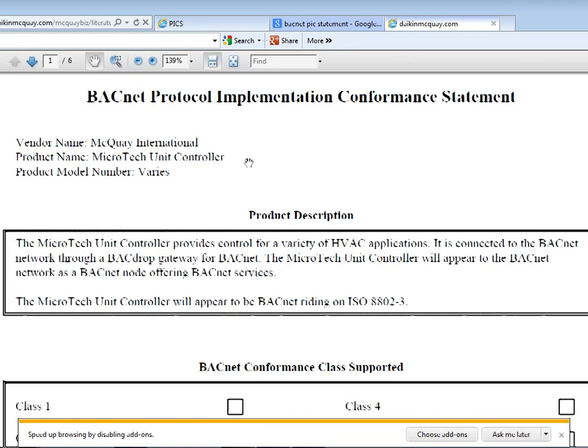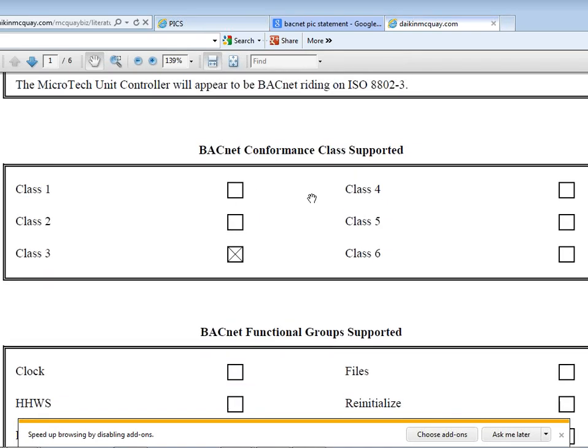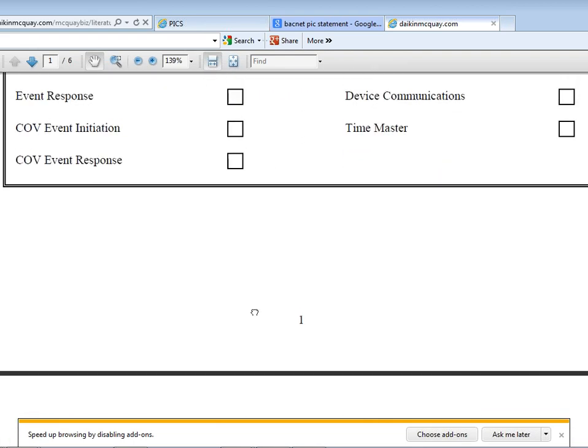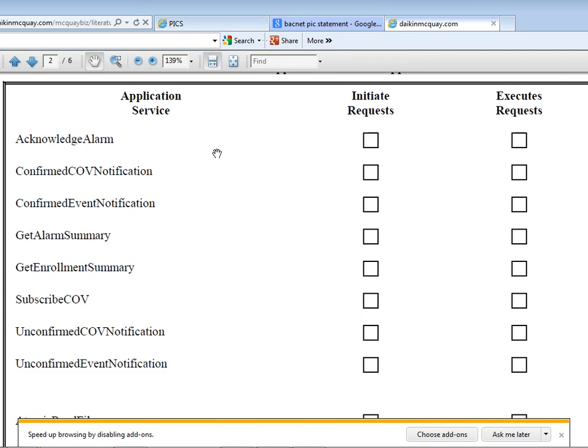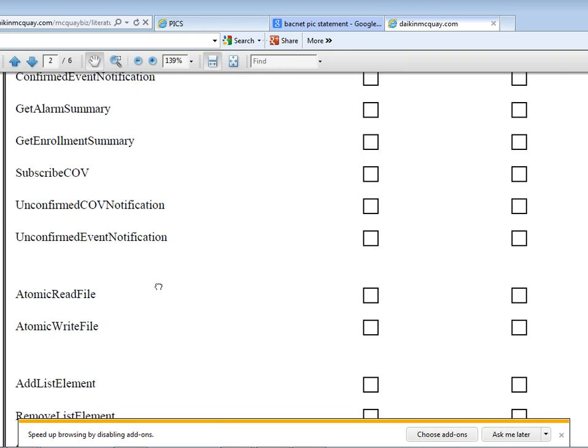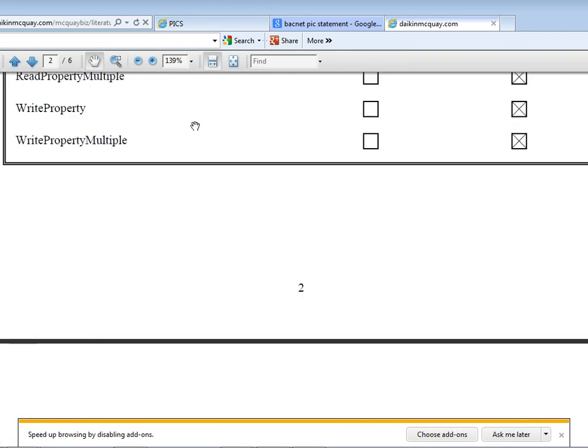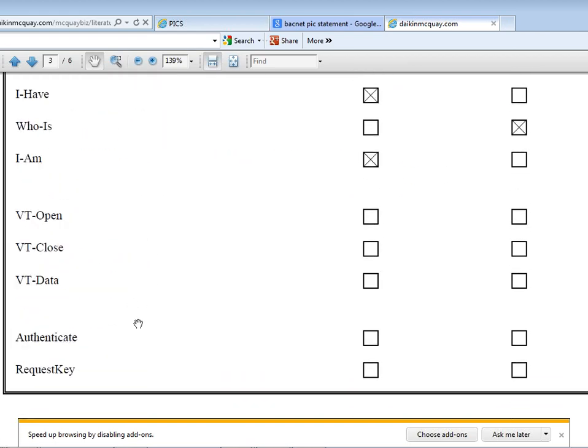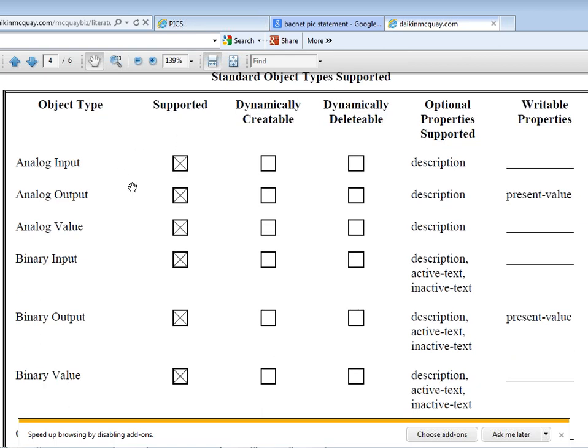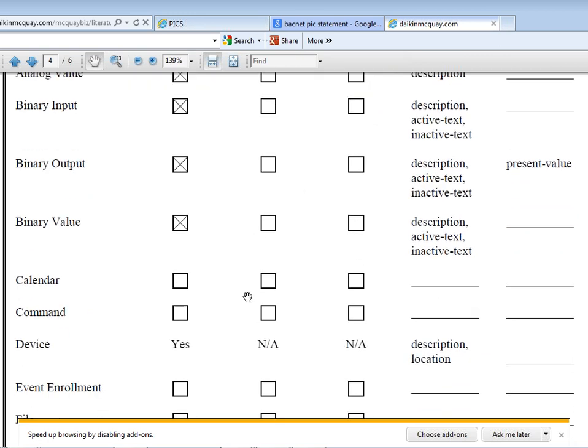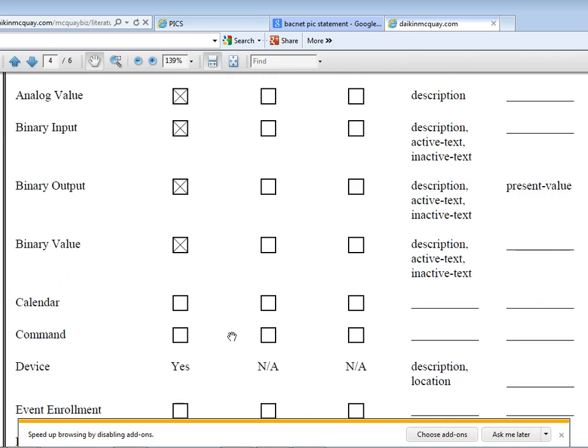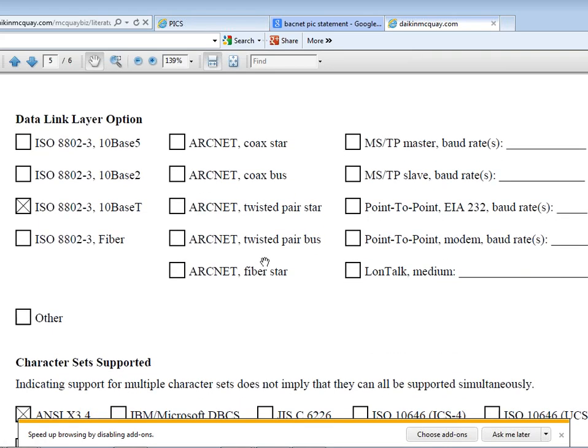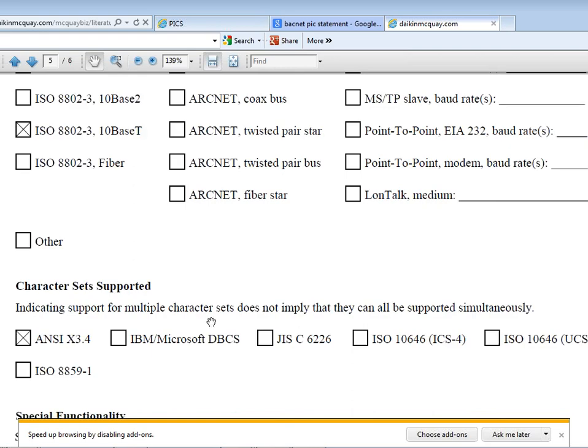This looks like a McQuay PIC statement. You've got your vendor name, product name, the class of BACnet conformance, functional group supported - these are the different types of services they can provide, like acknowledge alarms, notifications, create objects, read writes, and all the different object types available. They won't specifically go into the points and object names - for that you have to go to the manufacturer's literature - but these are all the object types supported via this controller. Then you have the different transport services you can communicate with, like ArcNet, MSTP, ISO, LAN, etc.